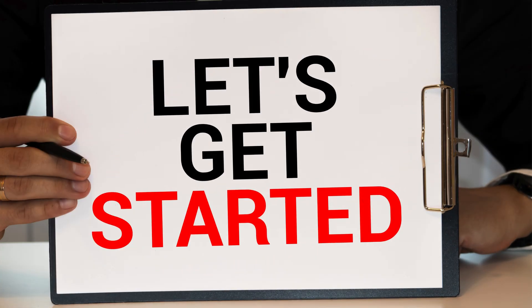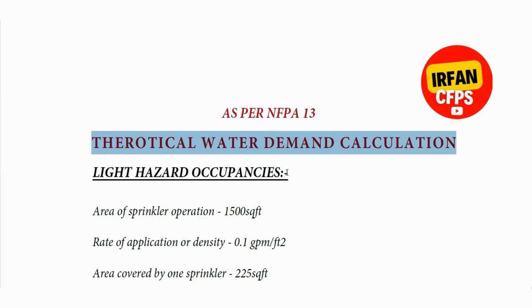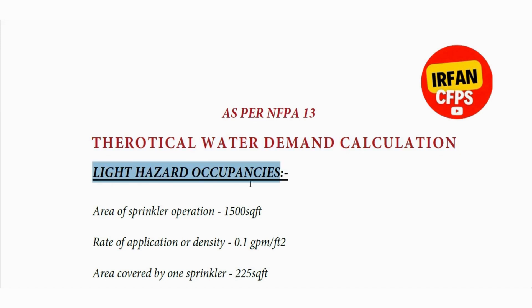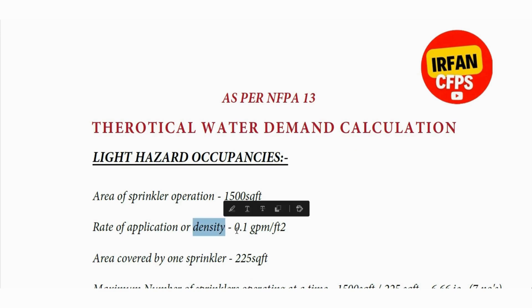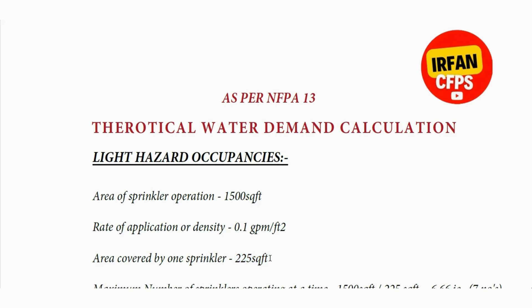As per NFPA 13, we are going to calculate the theoretical water demand for a sprinkler system. Based on light hazard occupancies, the area of sprinkler operation or design area will be 1500 square feet. As per area-density curves, the rate of application or density will be 0.1 GPM per square foot. The area covered by one sprinkler for light hazard occupancies per NFPA 13 will be 225 square feet.